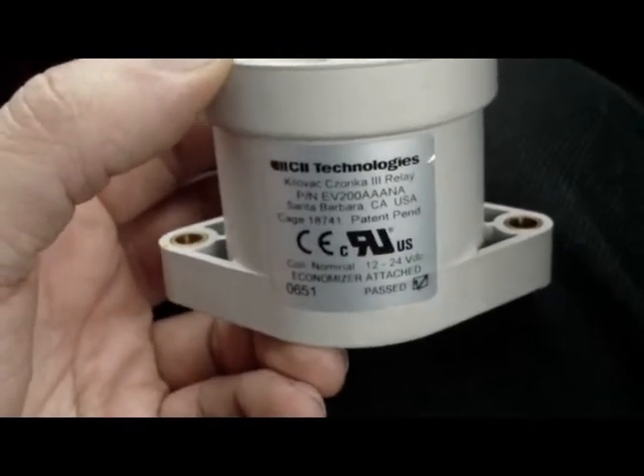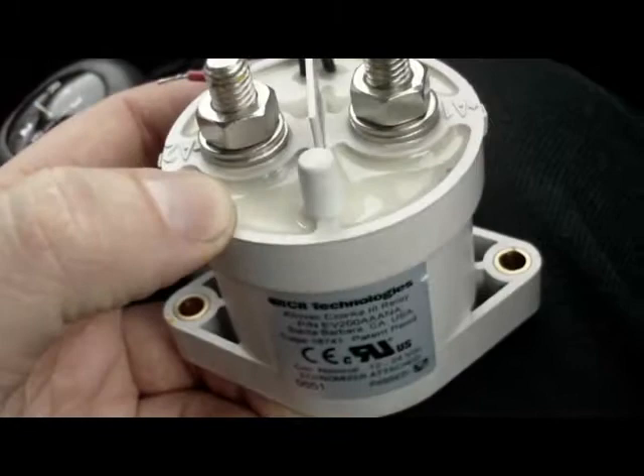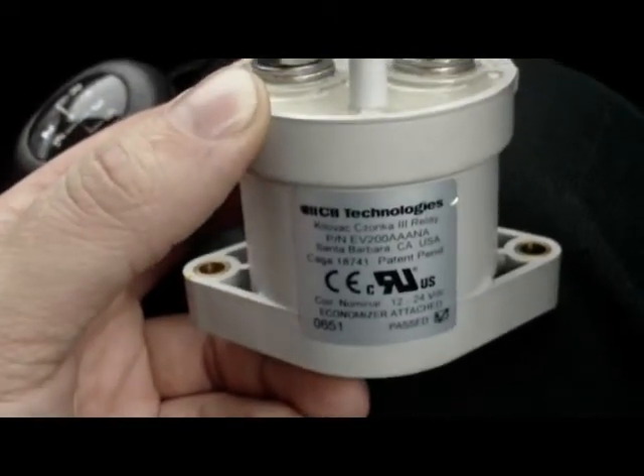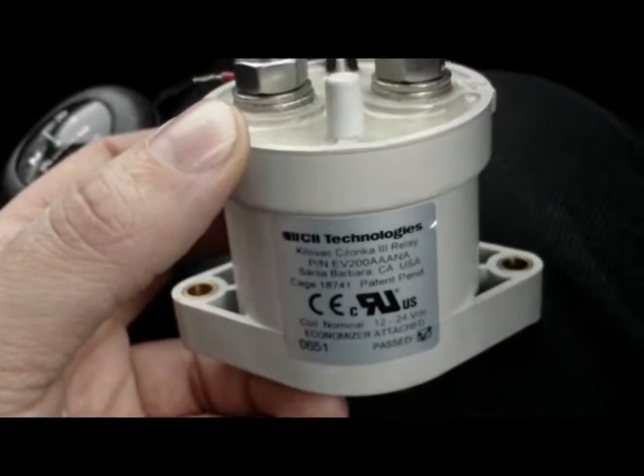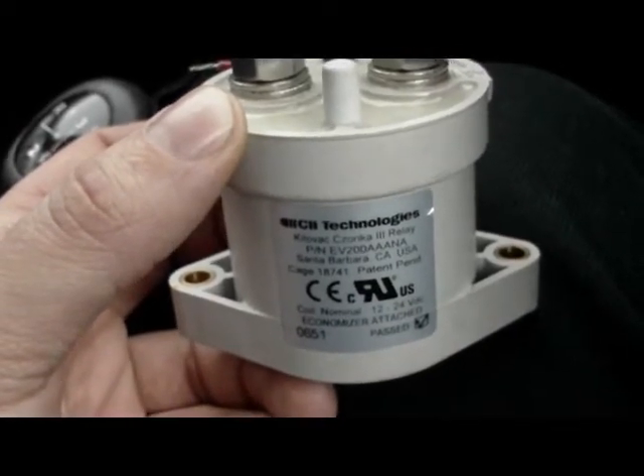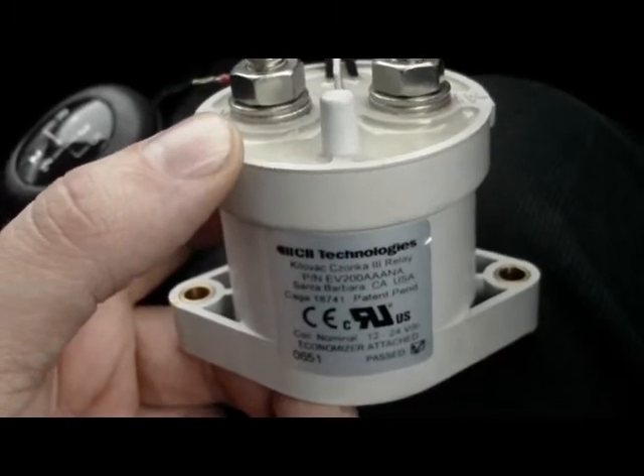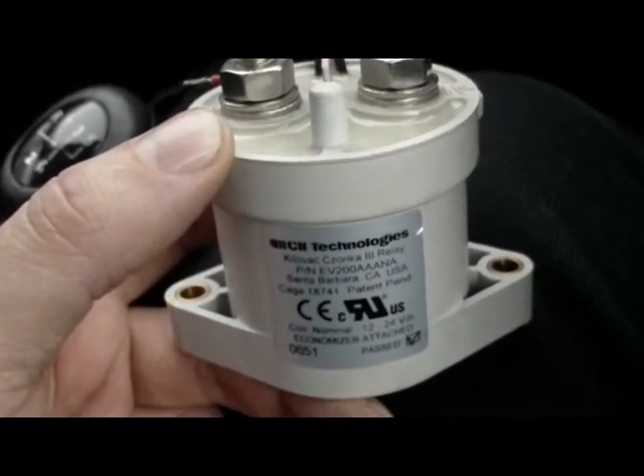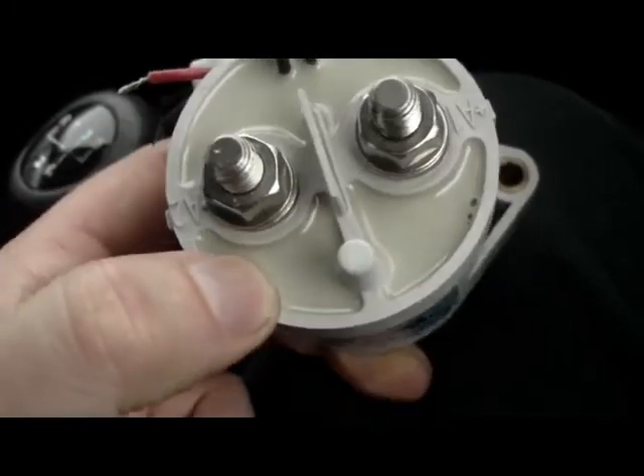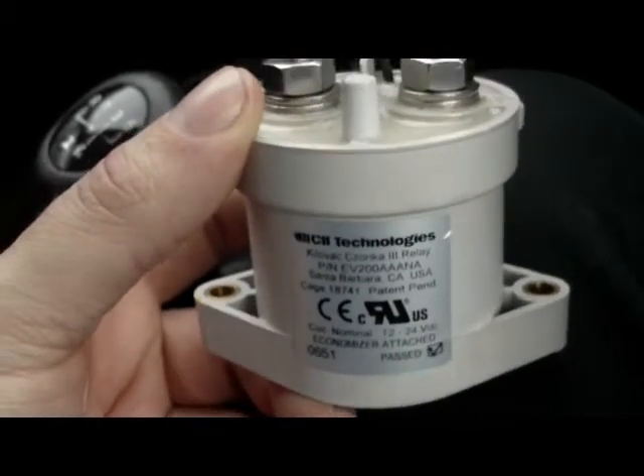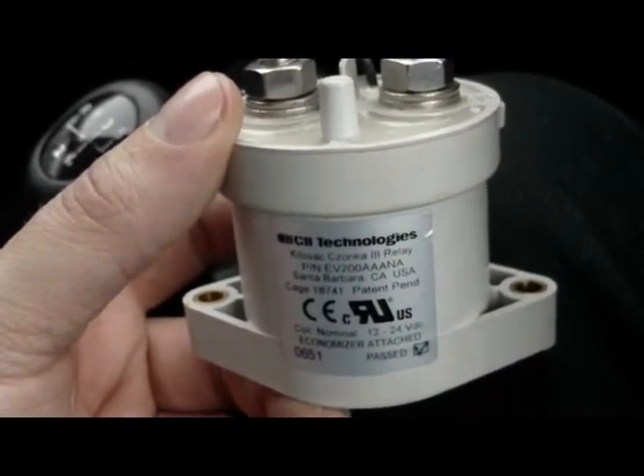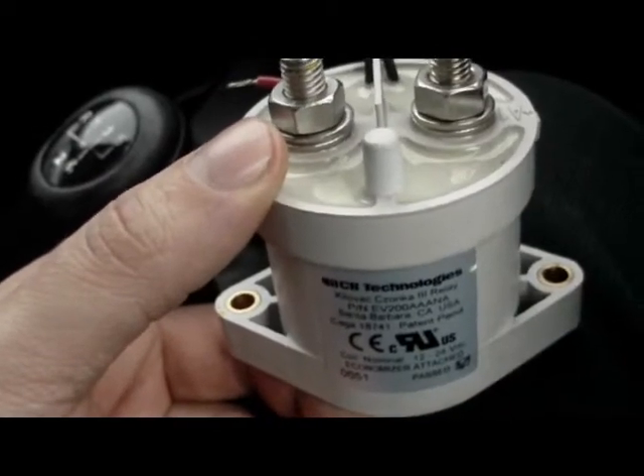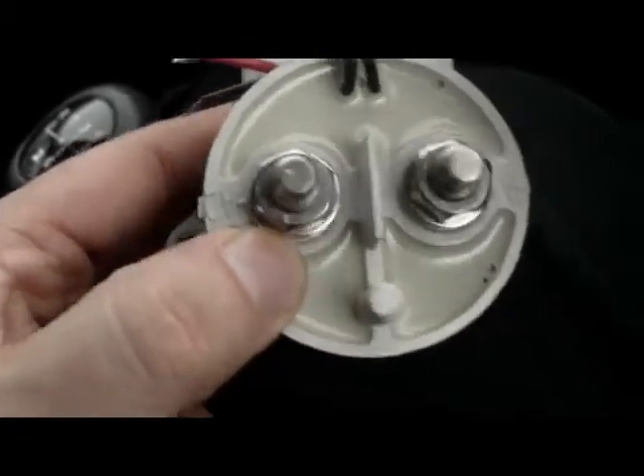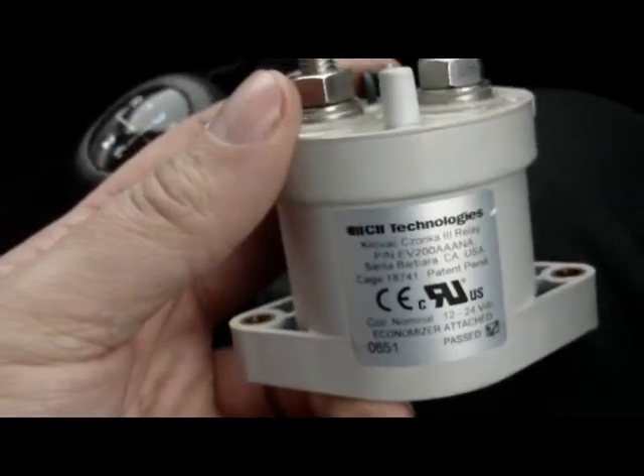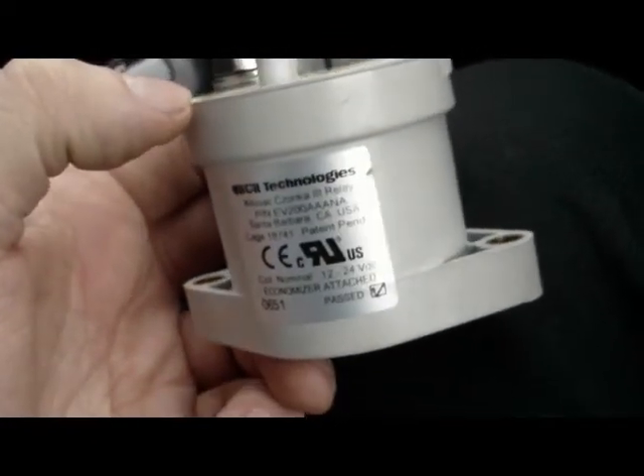They're quite a powerful piece of kit in a very small package. This can carry 500 amps at around 300 volts DC, and it can break a 2000 amp circuit at 320 volts DC also. I happen to have two of these in the traction feeds for disconnecting power, and also as part of the emergency shut-off, to break the traction circuit in case something goes pear-shaped.